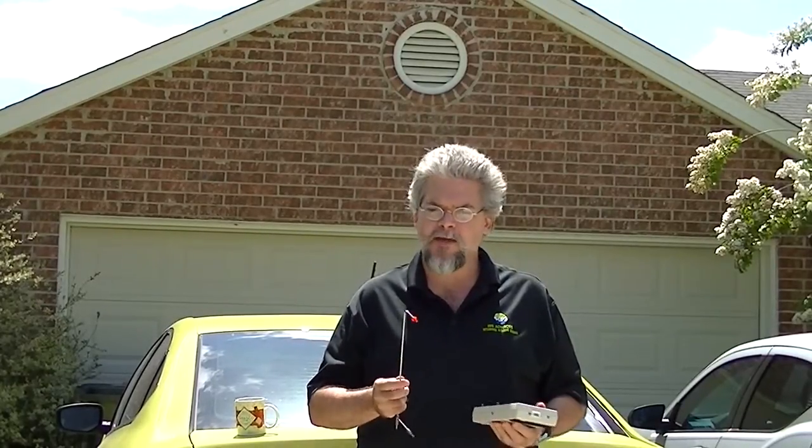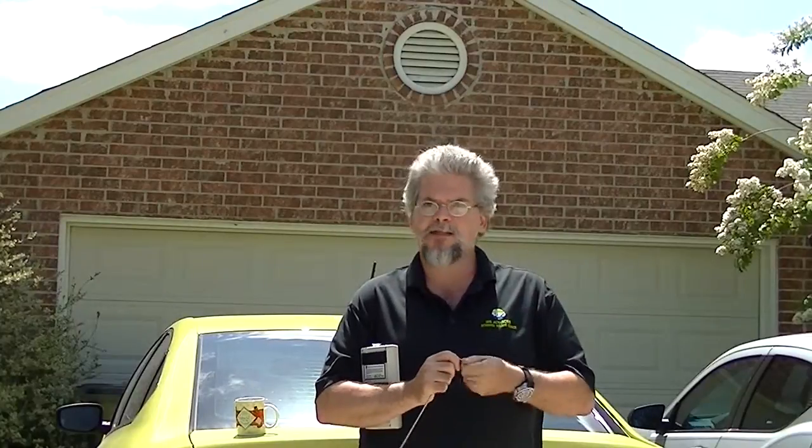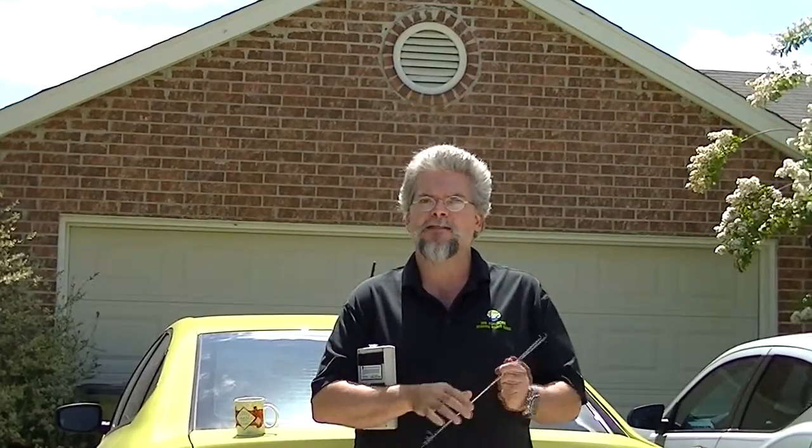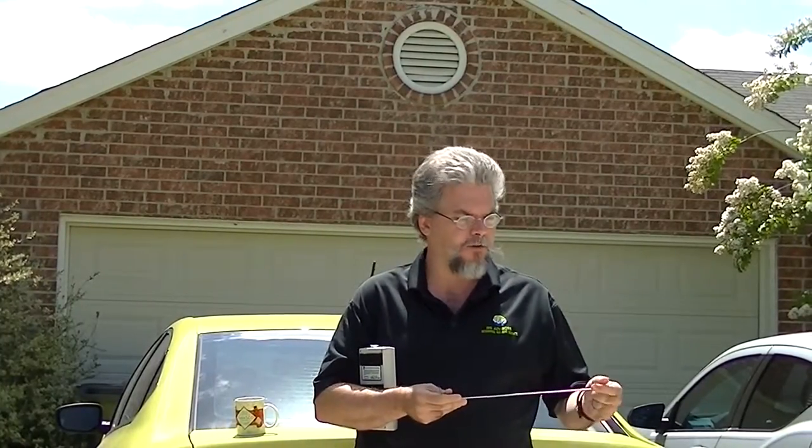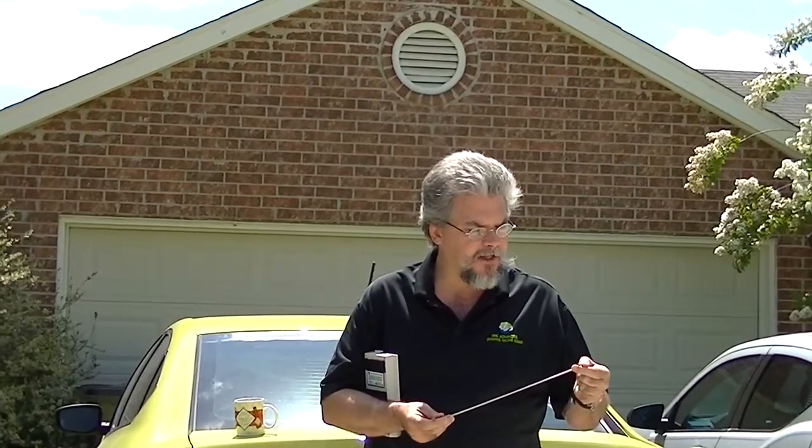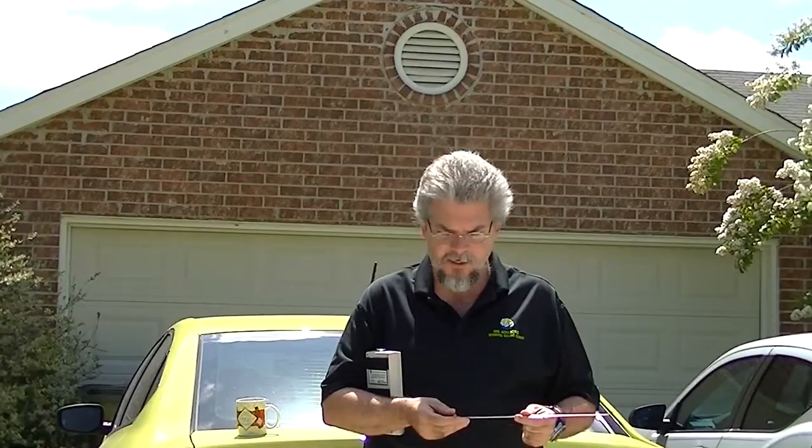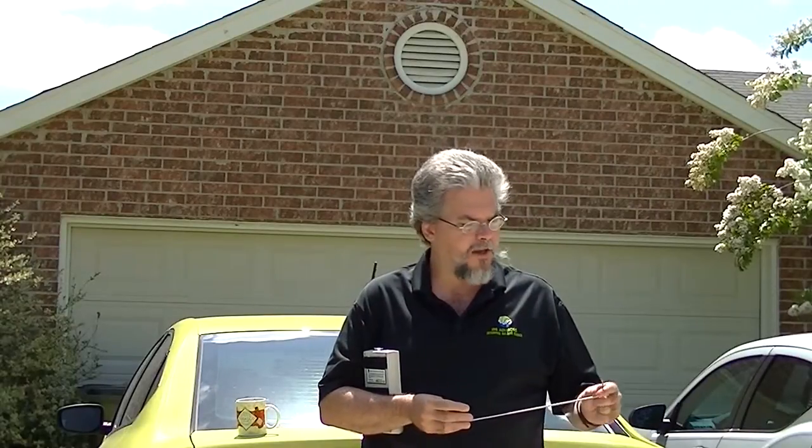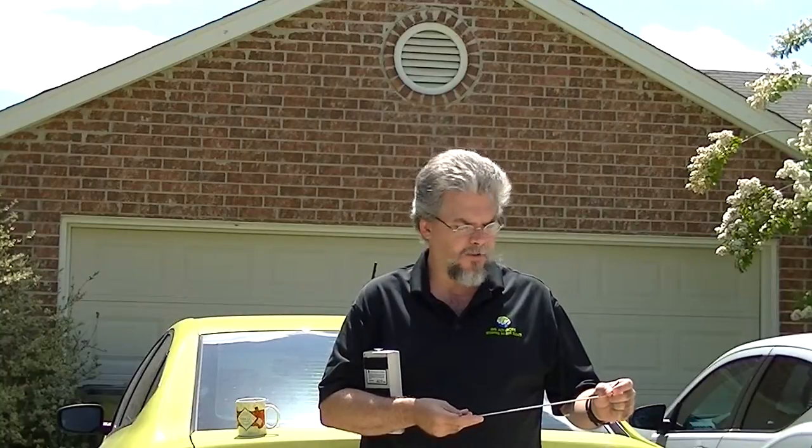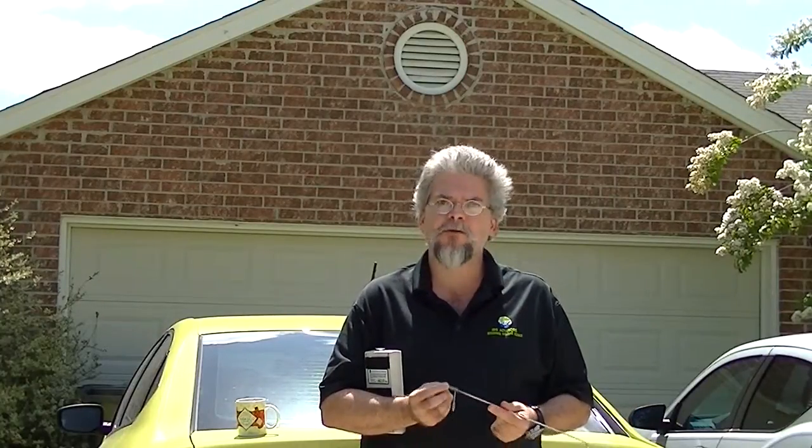This pitot tube is basically a static pressure pitot tube and a stagnation pressure pitot tube combined. It has little tiny holes along the sides that connect to this pressure tap, and a hole inside the tip like a stagnation pressure probe that connects to this tap.